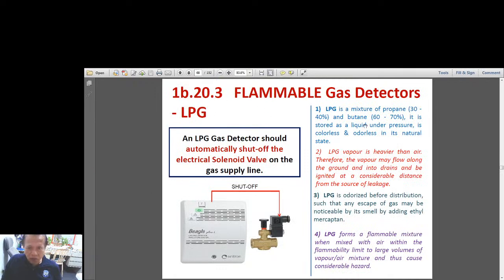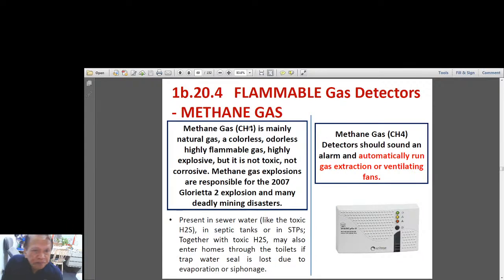Okay, LPG is also a dangerous gas, so it must be provided with a detector. Here is a detector, and here is a solenoid valve, an electrical solenoid valve that will automatically shut off the flow of LPG gas to an appliance like an LPG burner, or maybe a dryer for a laundry or other purposes. And here is methane.